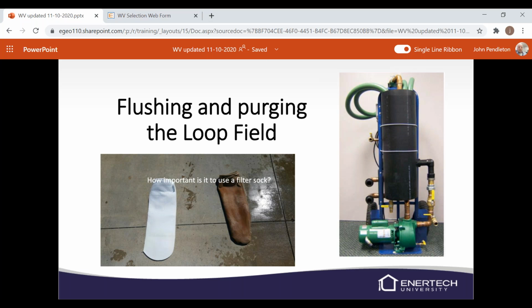I ought to put the new picture in here. It's a real nice flush cart. We made the flush cart that's in this picture, and we made the ones that we would sell before, but now we're actually getting our flush carts through Geoflow, and they're real nice. They have a sight glass on the side with a little marker, so you can mark it and see if you're dropping the level in your flush cart when you deadhead the pump. It's got a way to even power flush with the new flush cart. So it's a really nice flush cart. I'll try to get that picture switched so people can see that next time. But I do have a flushing and purging video on YouTube that has the new flush cart, so you can check it out there.